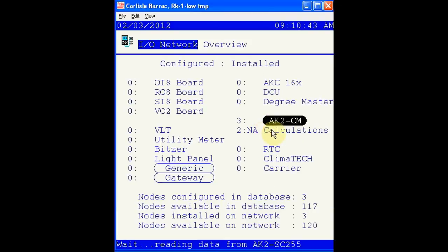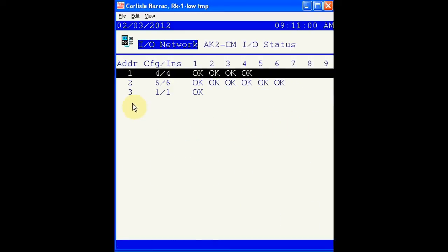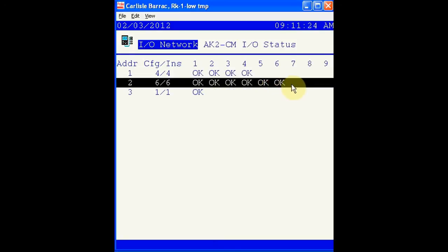Overview can be very useful if you are having trouble keeping boards online or troubleshooting. As you can see, there's a button on the right that allows you to get more details on AK2 communication modules shown here. Here we see 3 communication modules. Those IDs are 1, 2, and 3. The screen shows communication module number 1 has 4 boards, number 2 has 6 boards, and number 3 has 1 board. The OK status means that communication is active and no boards are lost. We can go one level deeper on any of these communication modules by selecting the address and pressing enter.